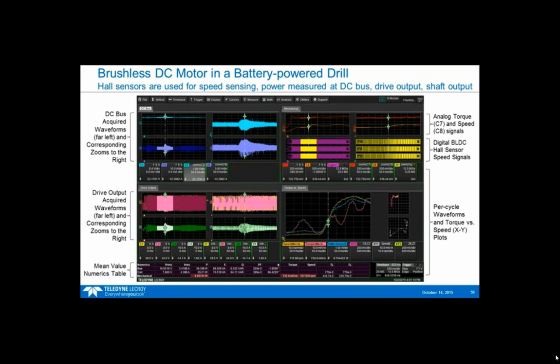So our current probe is DC to 50 or 100 megahertz, depending on the rating for 30 amps, and that's all you need. So as long as you can get a signal that represents voltage through a probe and a signal that represents current, either through a BNC cable or a probe into our motor drive analyzer, you can measure all that, and then the DC bus values appear right here in the same table. And of course, then if the drive output follows bus, I can calculate efficiency from the drive output to the bus, and so on and so forth.